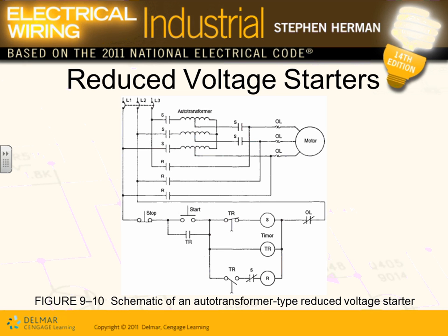Any comments? Here's what I want you guys to know without getting into the details. I want you to understand there are three ways of controlling a motor. Number one is across the line. This is just a magnetic starter, slam shut, and it's running. The other one, you reduce the voltage to reduce the inrush and the torque. The other one is speed controlling, which is also you reduce the voltage and the frequency to reduce the inrush and the torque, as well as control the speed.